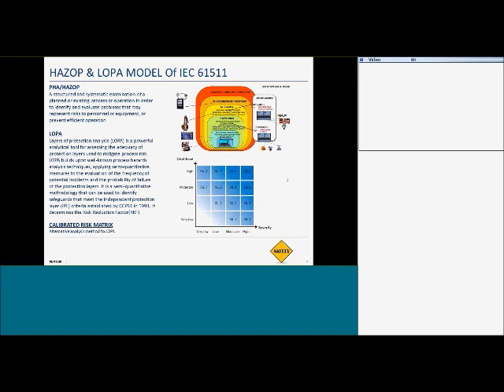Layers of protection is very important. For example, if they take a look at a heat exchanger and they have not got enough layers of protection around that heat exchanger, this is where they identify that they need to develop a more robust safety system, and it's also where they may be generating business for us, because through this process they determine they may need additional shutdown systems. That might include sensors, logic solver, and automated valve packages or final elements.